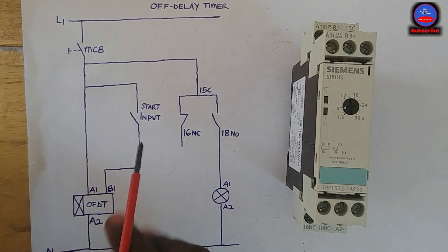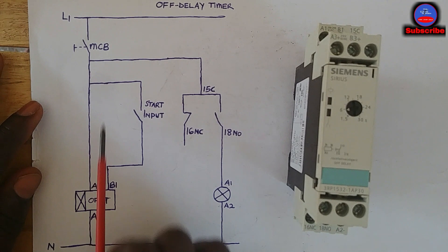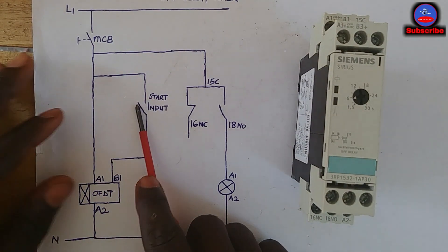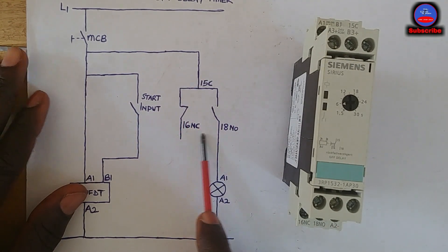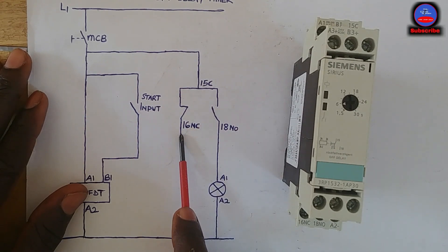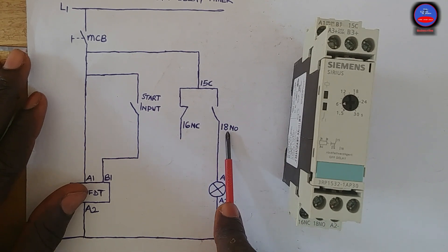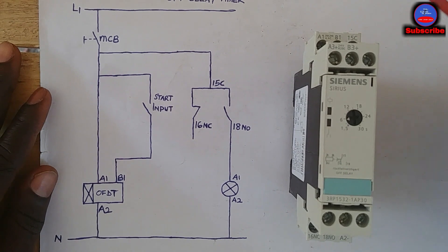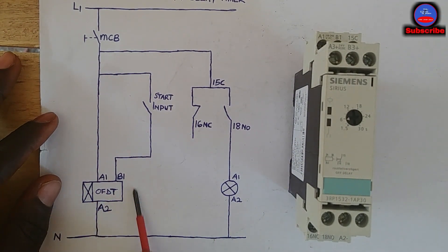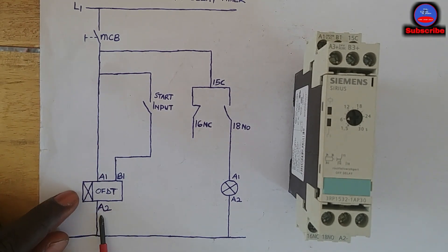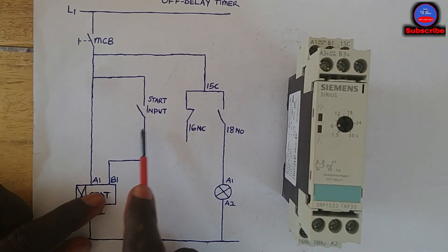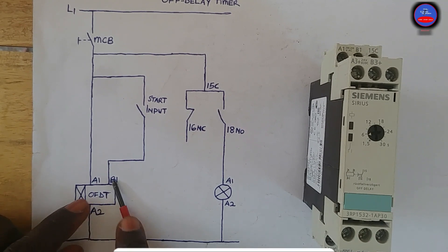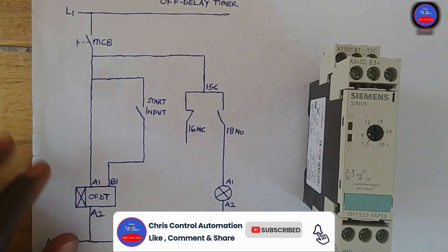In our circuit diagram we have the MCB — the main circuit breaker — the timer coil, the start input switch or push button, the contacts: 15C common, 16NC normally closed, 18NO normally open, and an indicator lamp. We are using the timer on AC so we only need A1 and A2. B1 is the input terminal for AC — I'll explain why it is there when we discuss off delay operation.